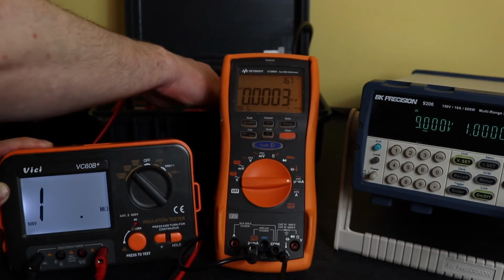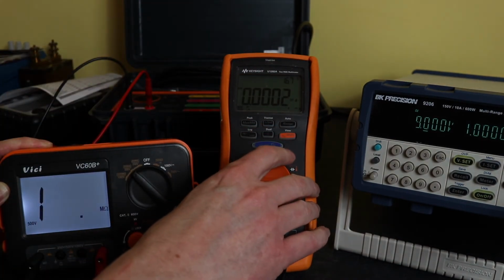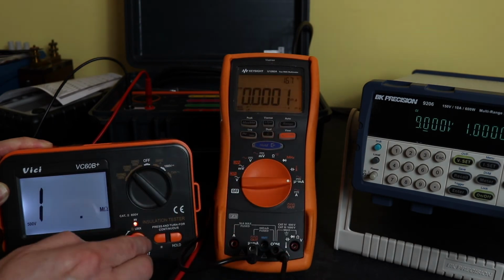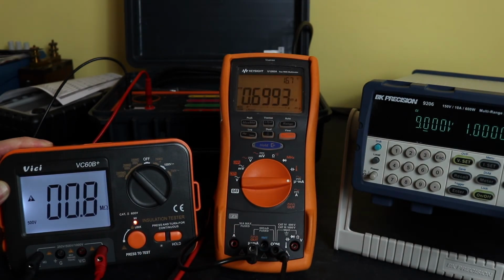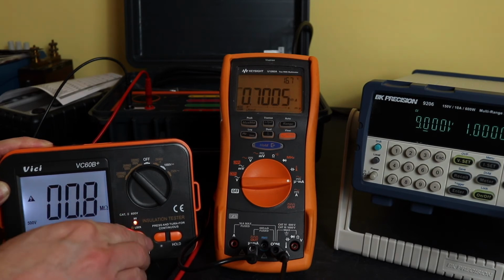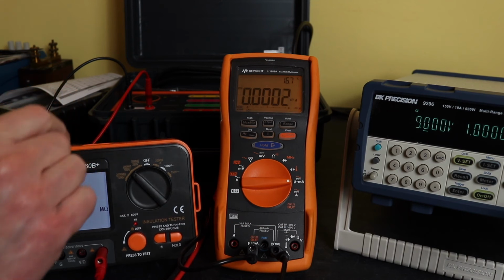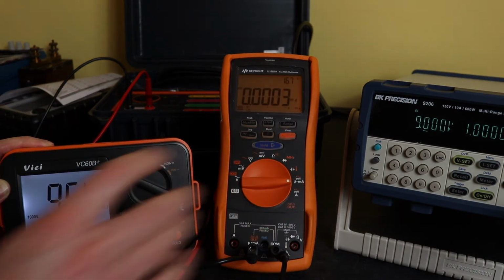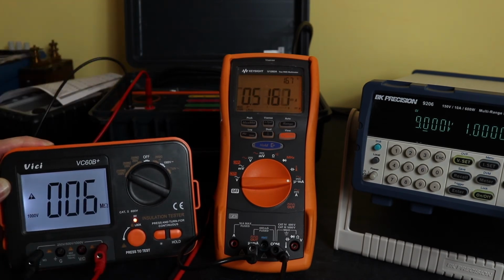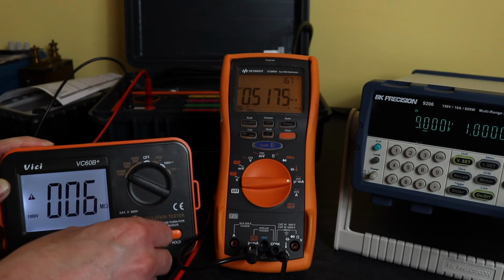We'll go 500 volt setting as well. Turn it back on, and again 0.7 milliamps. So again, not 1 milliamp. Also, this should be reading 500 kilo ohm on 0.5, and you can see the inaccuracy here that you've got. The final one, 1000. On to 1 mega ohm, and again only 0.5 milliamps out.